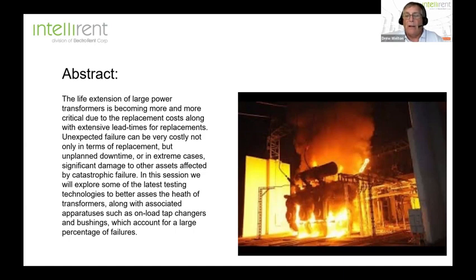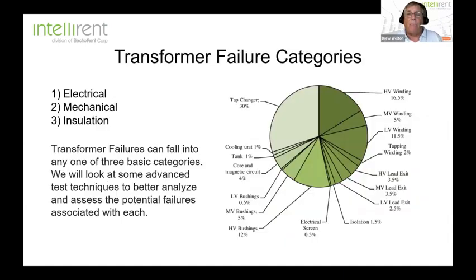And as Mark said, heat is not a good thing in any power system. And as you can see, this one's very hot. But we want to do everything we can to avoid failure, especially catastrophic failure, which can be extremely costly, not only in terms of that asset, but its surrounding assets that can be affected by such an event. So if we talk about transformer failure, there are certain categories. The three main categories are electrical failures, mechanical, and insulation. Basically, it falls into those three basic categories.